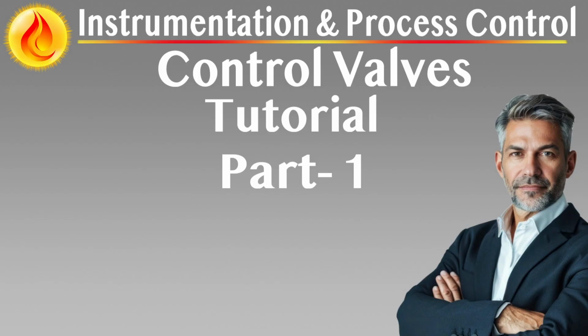Noise mitigation may include source treatments, special trims, diffusers, attenuators, path treatments, acoustic insulation, or increased pipe wall thickness, used sparingly due to cost. Selection must balance technical performance and economic viability in consultation with the valve supplier. Anti-cavitation valves. Where cavitation is unavoidable due to service conditions, anti-cavitation trims shall be used to prevent material erosion and hydraulic instability. These designs manage pressure drop across multiple stages, minimizing bubble collapse energy.